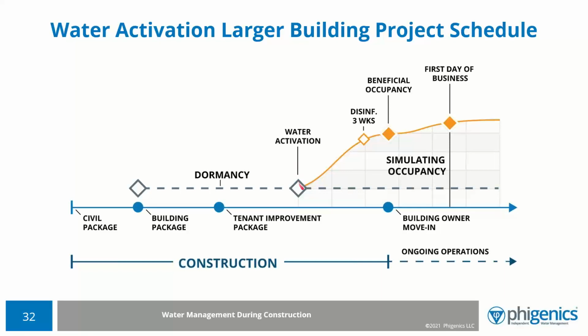What we've been working with clients on is how to write a program to simulate occupancy through flushing, either manual or automated systems, that raises the quality of the water so that at the disinfection point, 3 weeks before beneficial occupancy, you're already in a positive water situation. You have a program activating that water so when you hand it off, the building owner knows that water is safe.